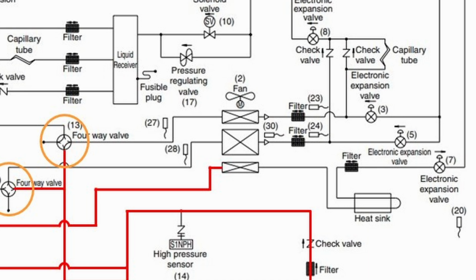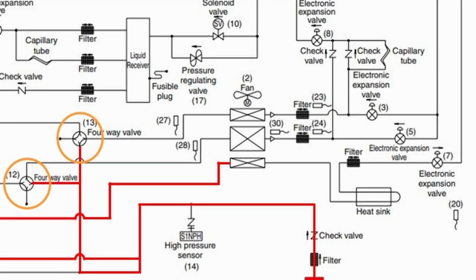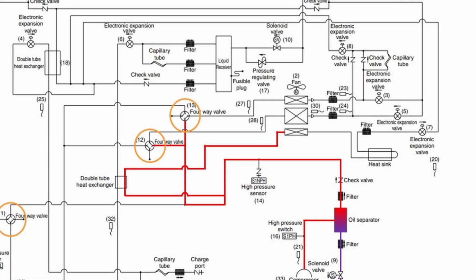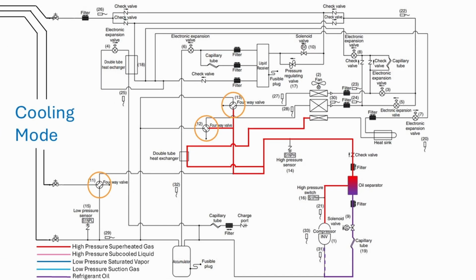So in this type of system, the 4-way valves not only control the mode of operation, but they also control the capacity of the system by regulating the amount of refrigerant through the outdoor heat exchangers. So the system only uses the amount of outdoor heat exchanger needed. In this example, the system is in 100% cooling mode, so the 4-way valves direct the refrigerant to the outdoor heat exchanger where we will use 100%.